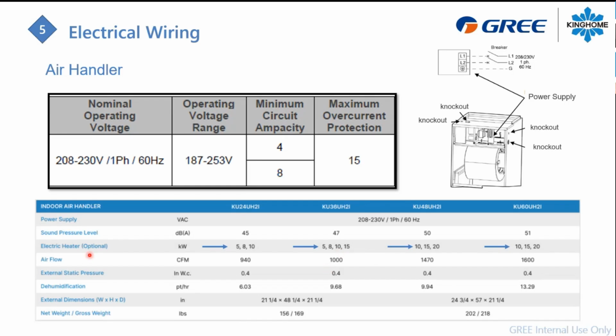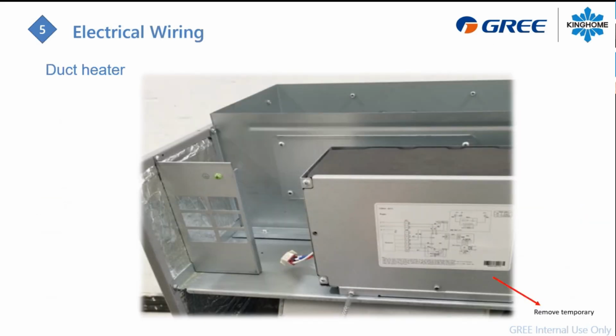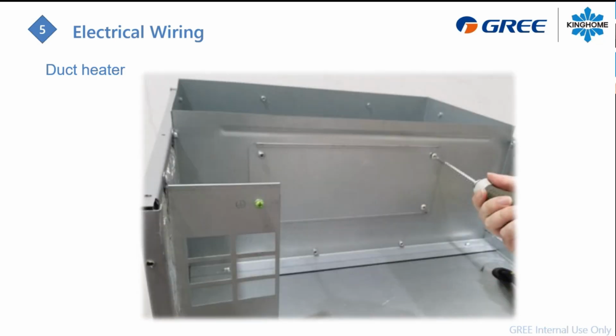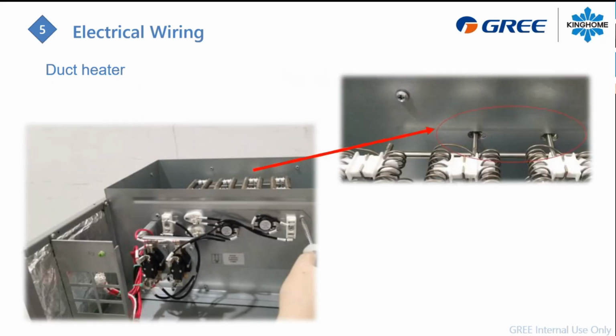If you install an electric heater, make a good check with the chart to see which one you can use and which one you can't, matching your air handler with your duct heater. Inside of the cabinet, it looks like this. In the picture the top panel is removed. You have the back plate here for the duct heater, a breaker holder, and this electrical box. If you need to install a duct heater, you will need to temporarily remove this box. Two screws hold it. That gives you enough space to access the back plate and install your duct heater.